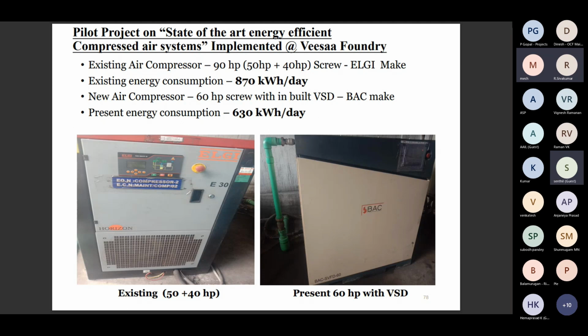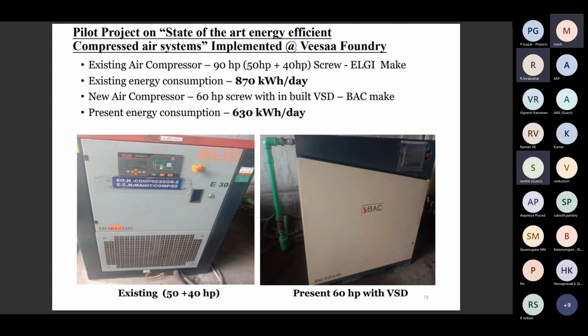The existing setup had 90 HP compressors, one of 50 and one of 40, consuming approximately 870 units per day. Now we proposed and implemented one energy efficient IPM model compressor, a BAC make with inbuilt VSD. It consumes only 630 units per day, so nearly 240 units are saved. Next.